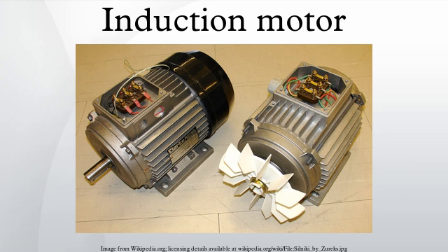Power factor. The power factor of induction motors varies with load, typically from around 0.85 or 0.90 at full load to as low as 0.35 at no load, due to stator and rotor leakage and magnetizing reactances. Power factor can be improved by connecting capacitors either on an individual motor basis or, by preference, on a common bus covering several motors. For economic and other considerations, power systems are rarely power factor corrected to unity power factor.